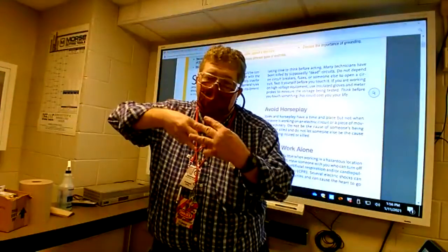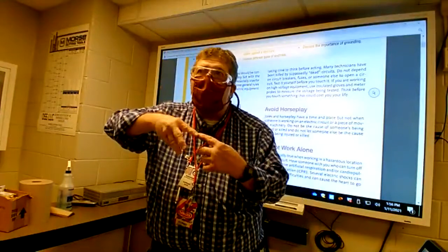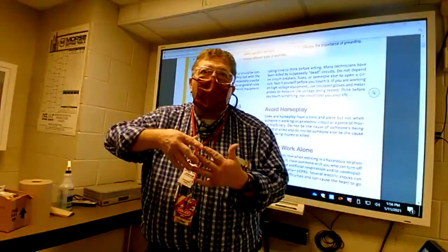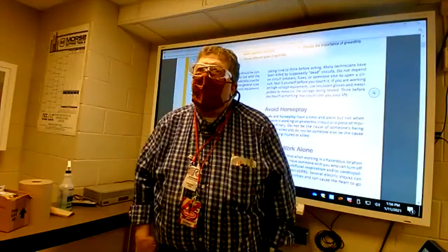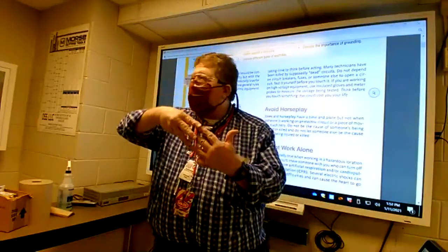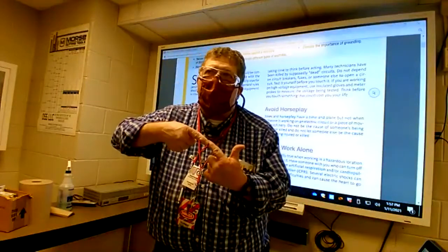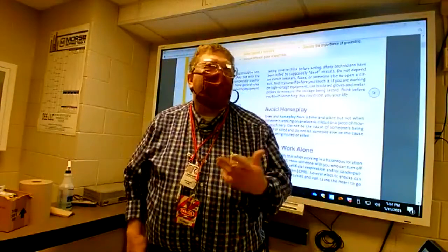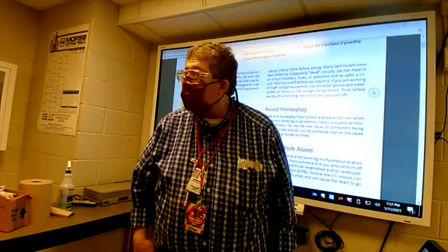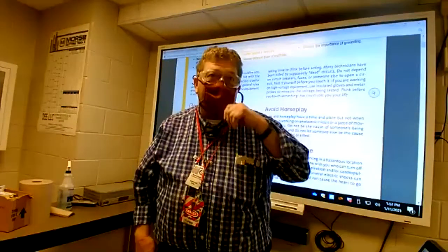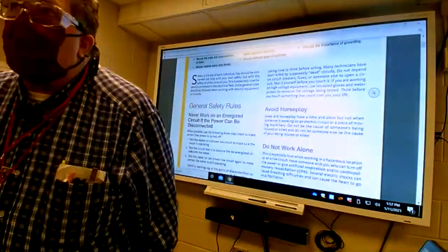Breaker contacts, whenever they make and break, after so many times, sometimes whenever they make, they weld themselves, and even though you cut the switch off, you might have one of the legs in there out of those three hot legs, one of them stays stuck or welded. That's what happened. Out of the three hot legs, the three phase power in that panel, when he cut it off, one of those legs had welded shut in that breaker, and it was still hot, and he happened to get a hold of it. You know, he lived to tell about it. He looked like he seen the ghost. You know, he was pretty shook up. So check it yourself with the meter.